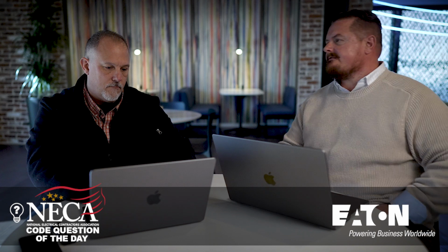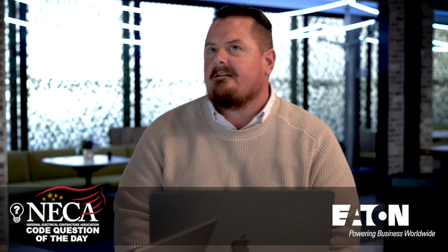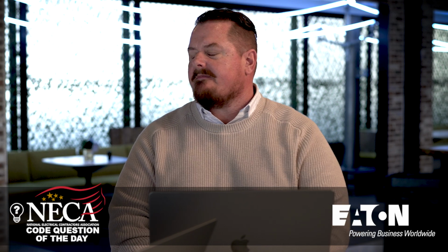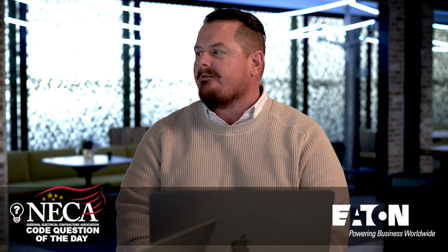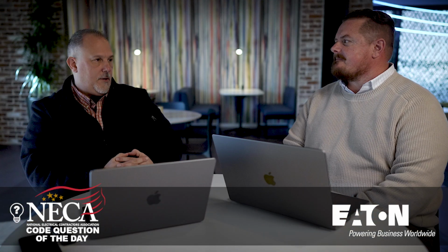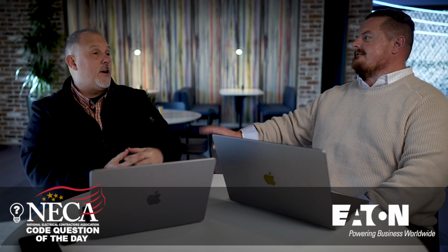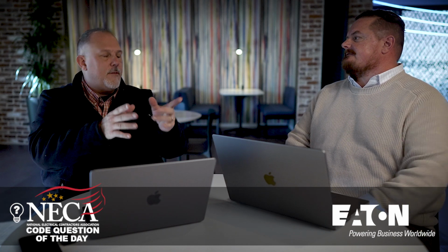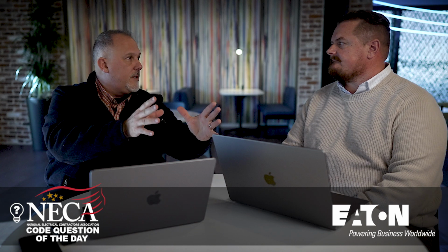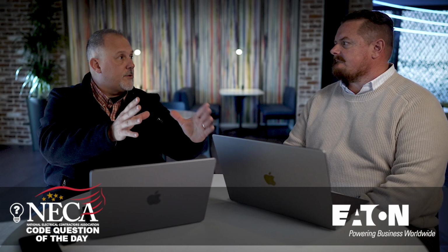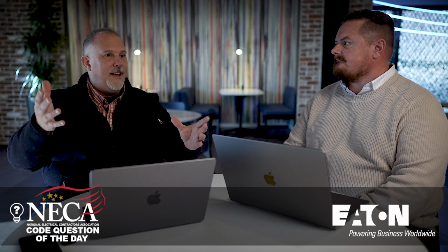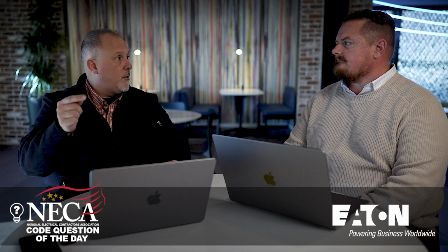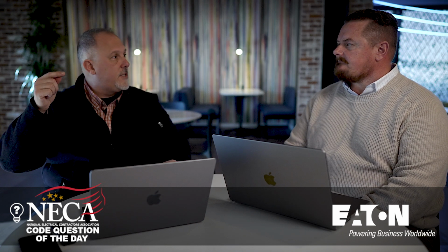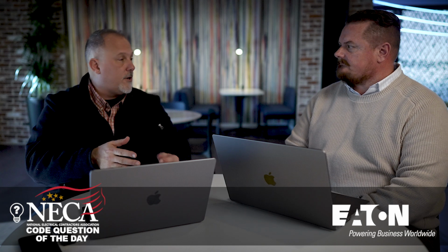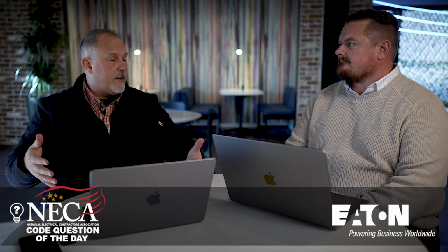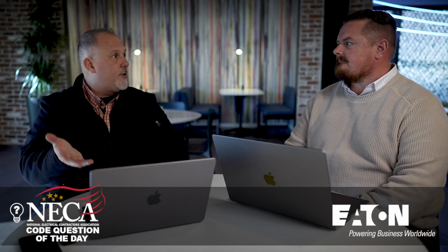So what are some other solutions that are out there? Maybe short of having the equipment field evaluated and rebuilt, what are some other solutions out there? One thing you could do, tell me, not to put you on the spot. No, I got two things. Put it this way. If I have a piece of equipment that has a 5,000 amp short circuit current rating and I've got 10,000 amps, if I'm not going to change the equipment, then I need to lower the fault current. So I either tell my electrician to take a few laps around the block with the conductor to lower the fault current, because conductor length will lower the fault current just because of the impedance, or I can put in a 1-to-1 transformer.